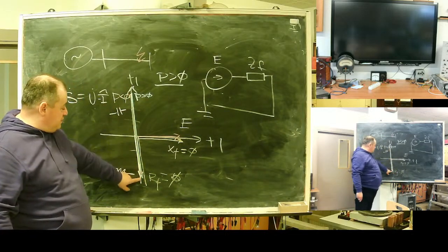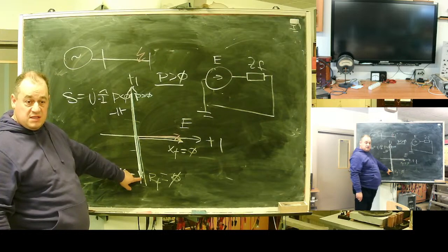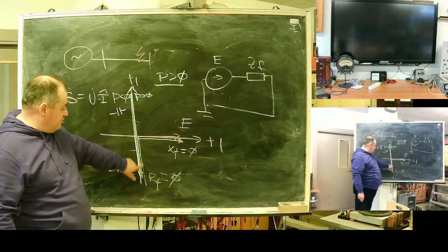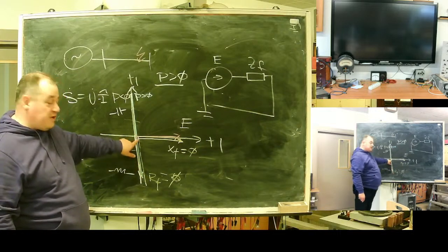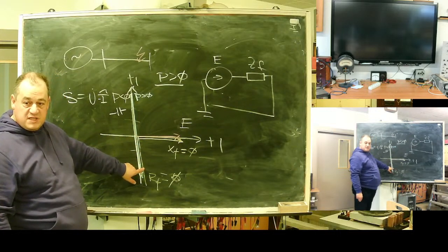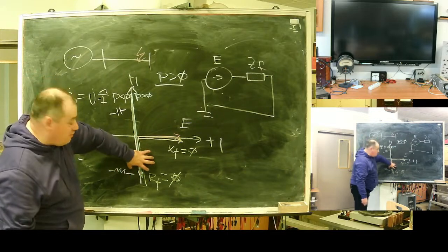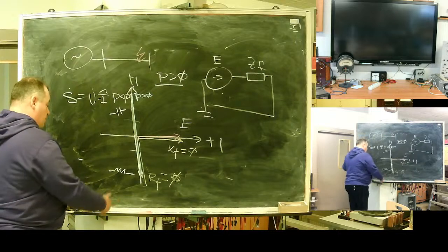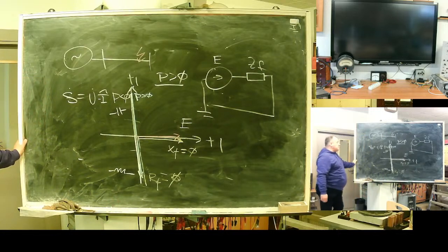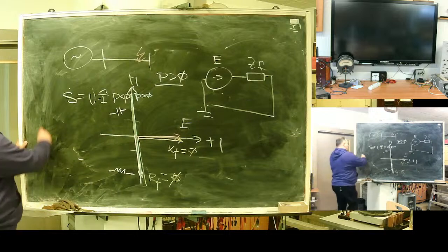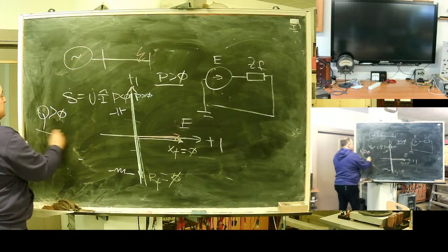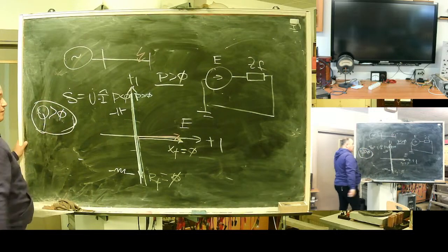How good is this method characteristic? Not very. You see, here we are in an area where we have no safety margin. Here we are not safe. What can we do? First idea, let's take not the active power meter, but a meter of reactive power. Let's assume something like this.